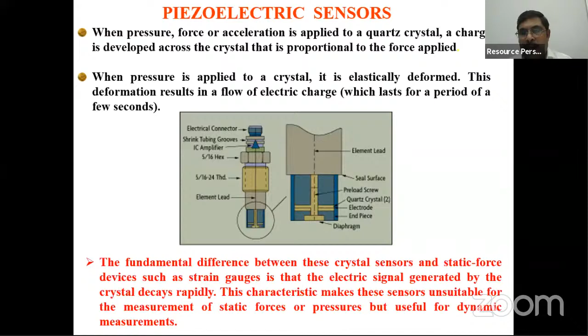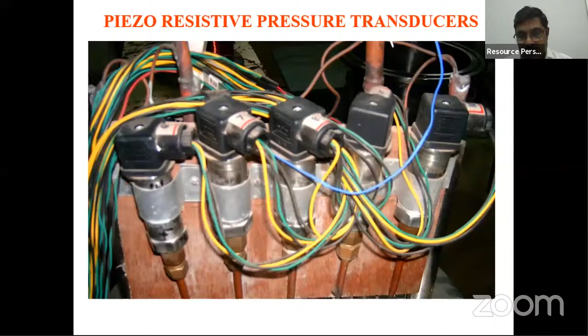If you are not calibrating the sensor periodically, you will end up with wrong results. Don't think that once you purchase the sensor and fit it into the experimental setup, it will always give the correct value. Every 6 months you need to calibrate the sensor, because these crystals, once subjected to repeated strain, will show a drift, which needs to be measured periodically. You can see here a photograph of this sensor.